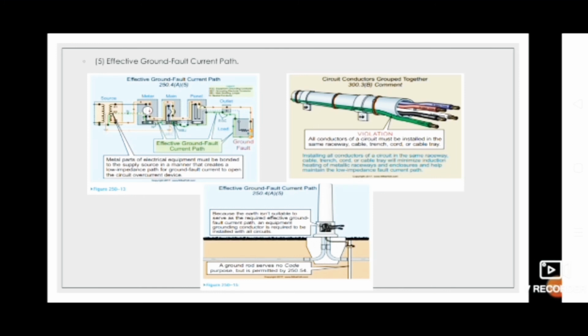Because the earth is not a low impedance path for fault current and is not suitable to serve as the required effective ground fault current path, an equipment grounding conductor of a type recognized in 250.118 is required to be installed with all circuits, as we can see in the picture.